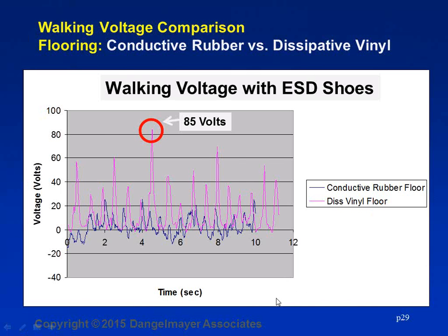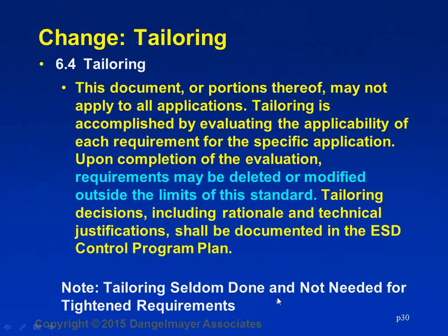Right, and I would also add that for compliance verification, you should check those areas that get a lot of high traffic, that perhaps the floor is dirty, or if it's a surface treatment, it might be worn. And so that would give you confidence by testing in the most difficult areas. If you're still within your specification, then you'll have more confidence that your program is designed properly and being maintained properly. So now we're going to switch to talking about tailoring.